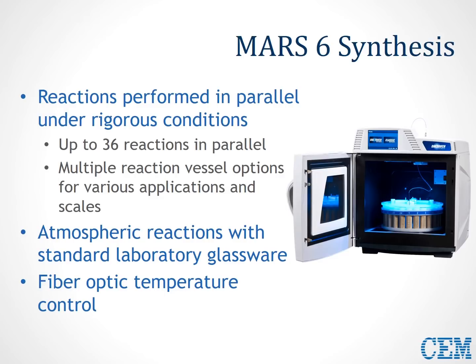Temperature for these batch reactions is measured in what we call the control vessel. All reactions on a vessel carousel should be exactly the same, so a fiber optic probe is inserted into one vessel for temperature monitoring. For analytical chemistry, an IR temperature sensor is also used to monitor temperature in the vessels, but for our purposes, a fiber optic probe is used.